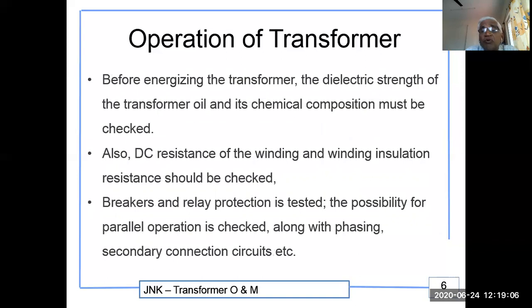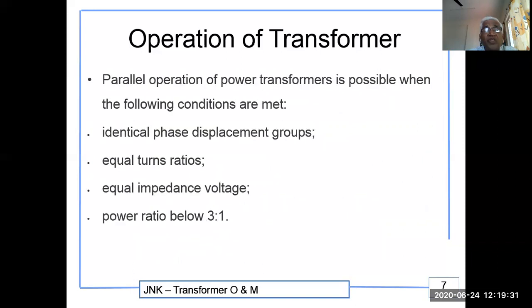Before energizing the transformer, the dielectric strength of the transformer oil and its chemical composition must be checked the first time when you are doing it. Also, the DC resistance of the winding and the insulation resistance should be checked. Breakers and relay protection are tested. The possibility of a paralleling operation is checked along with the phasing, secondary connection circuits, etc. Parallel operation of the transformers is possible when the following conditions are met: identical phase displacement, equal turns ratio, equal impedance voltage per kVA, and power ratio of something like below 3:1.